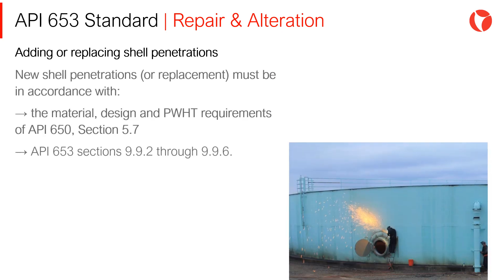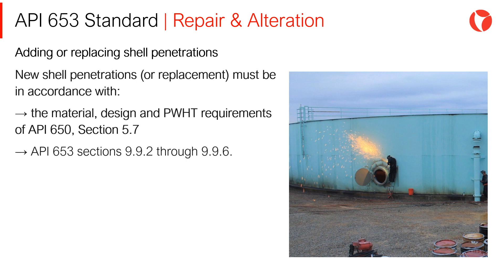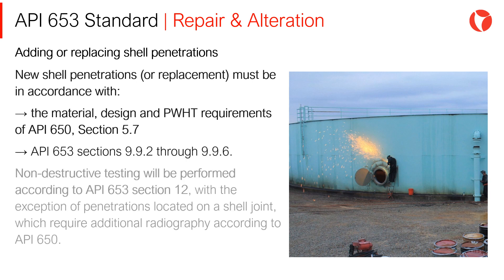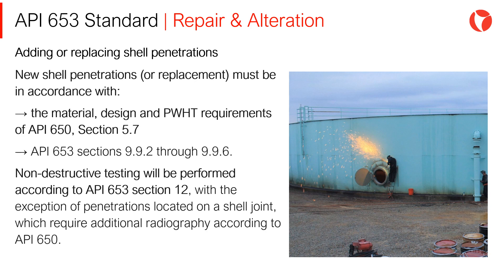Adding or replacing shell penetrations: new shell penetrations, or replacements, must be in accordance with the material design and post-weld heat treatment requirements of API 650, Section 5.7, and also with API 653 standard sections 9.9.2 through 9.9.6. Non-destructive testing will be performed according to API 653 section 12, with the exception of penetrations located on a shell joint, which require additional radiography according to the API 650 standard.